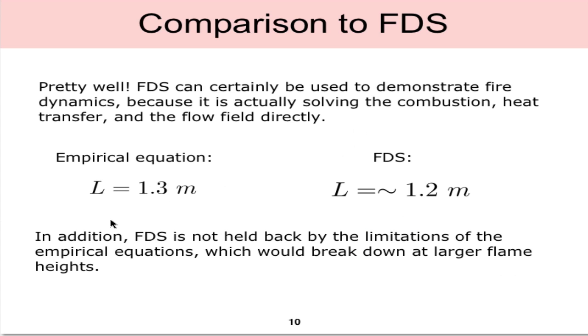How well does that compare to our empirical answer of 1.3 meters? It turns out that it's pretty good, pretty close. 1.3 meters, 1.2 meters. In this case, FDS can certainly be used to demonstrate fire dynamics because it's actually solving the combustion, heat transfer, and the flow field directly, whereas our empirical equation is using previous data sets to estimate what the flame height would be.